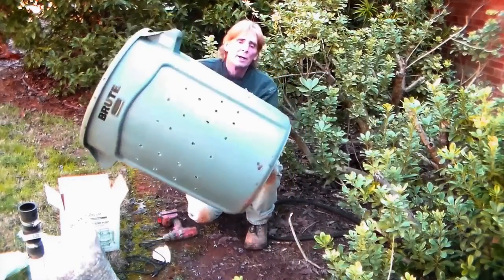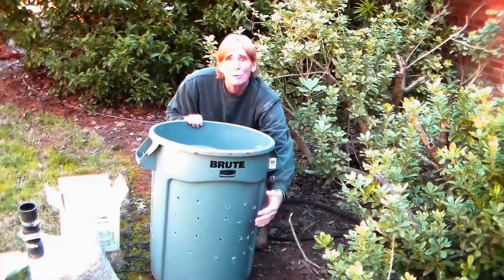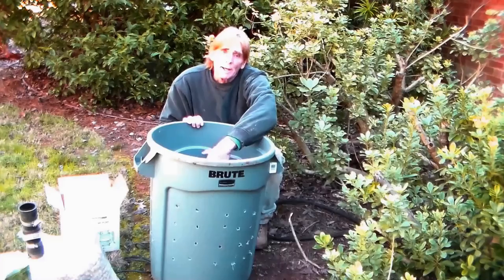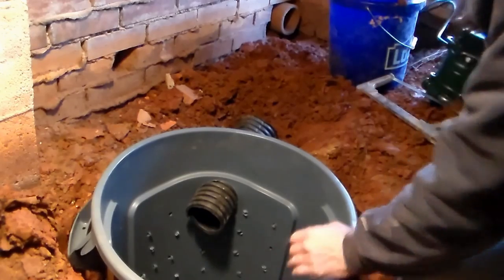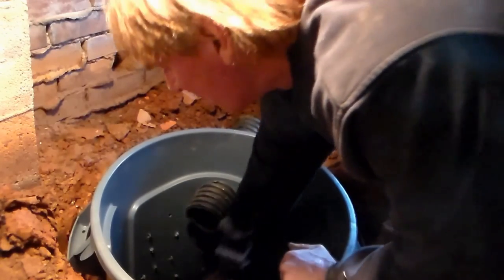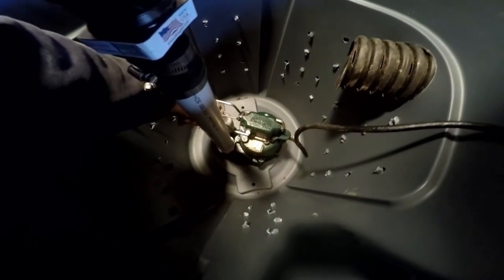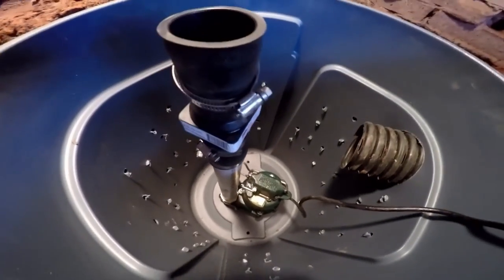You can see all the holes we just put all over this sump liner. What that does is allow water - there's going to be gravel outside, water comes through the gravel, enters through the holes into the pit, and the sump pump lifts it up and carries it away. We go ahead and set our sump pump - the Zoeller M53 - down into the bottom of the pit. You can see the nice solid bottom. Our float, when it fills up with water, is going to kick on and off.